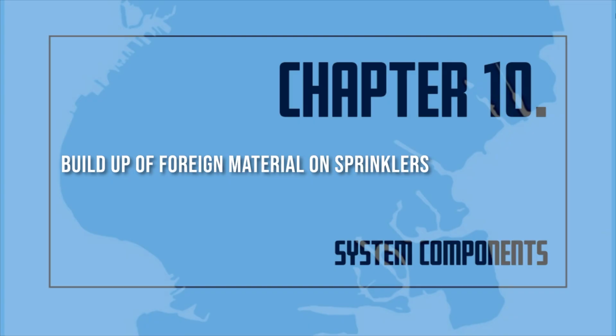This damage may prevent the sprinkler heads from working properly. The damage may also cause the sprinkler head to leak. Deposits of light dust are less serious than hard deposits. Dust buildup may delay the operation of sprinkler heads. However, it will not prevent the eventual discharge of water.